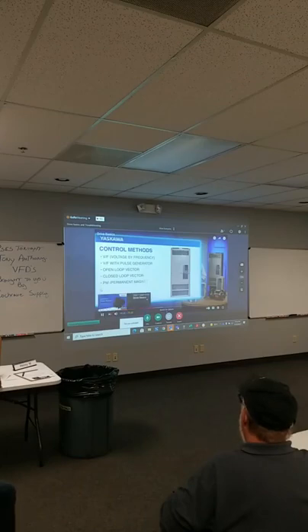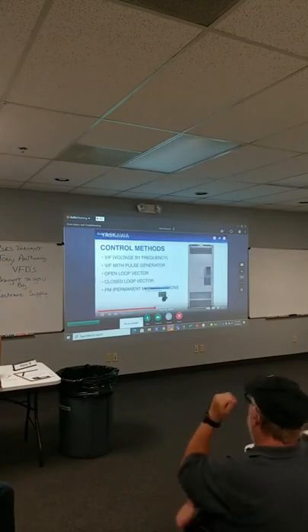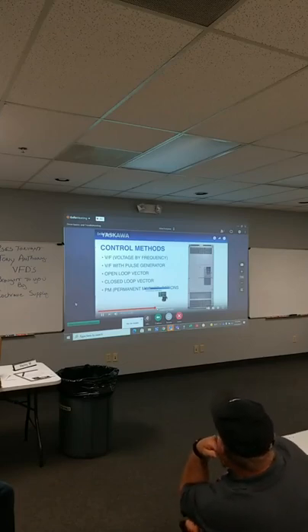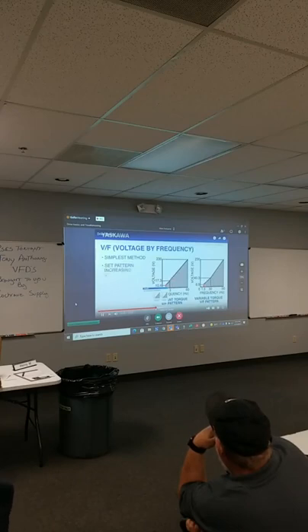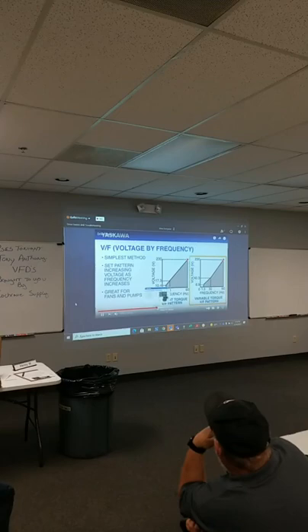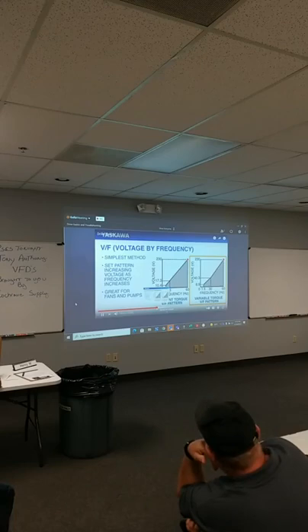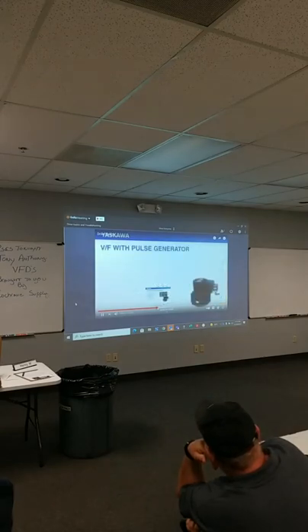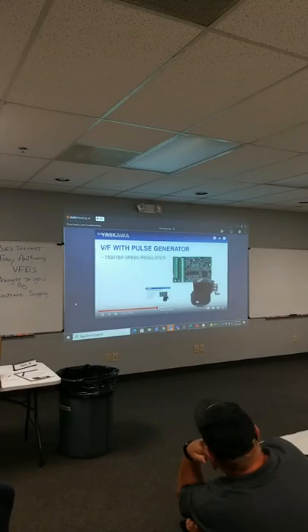As we move through each of these methods, control becomes better and better. VF, or voltage by frequency control, is the simplest method. This follows a set pattern, increasing voltage as frequency increases. It's great for fans and pumps, and it's also very good for applications that do not need tight speed regulation of the motor. When adding a pulse generator or PG feedback device, the speed regulation becomes tighter and the drive actually knows the speed and the direction of the motor. A PG is commonly referred to as an encoder.